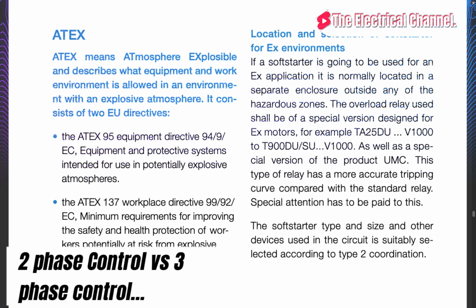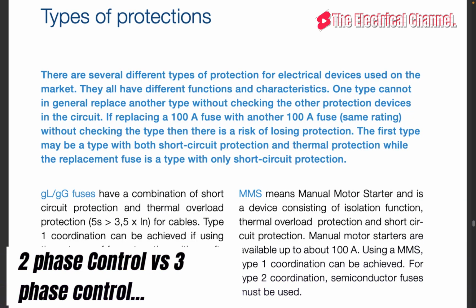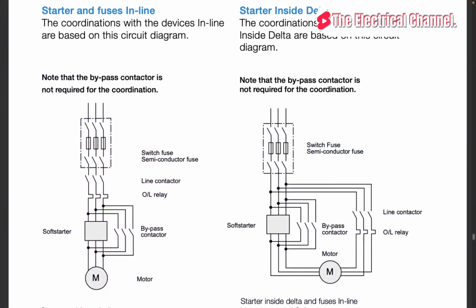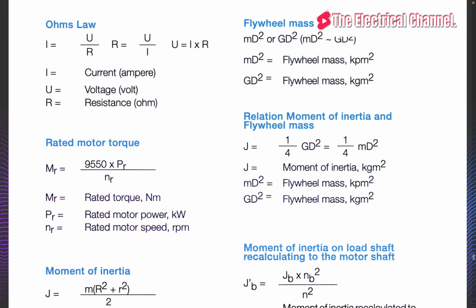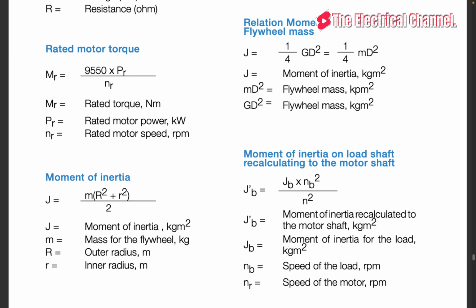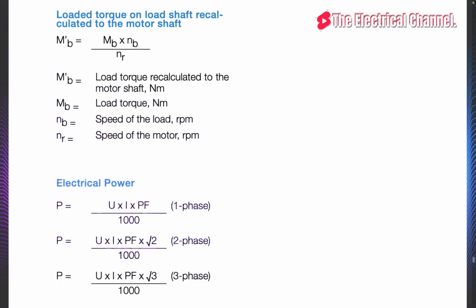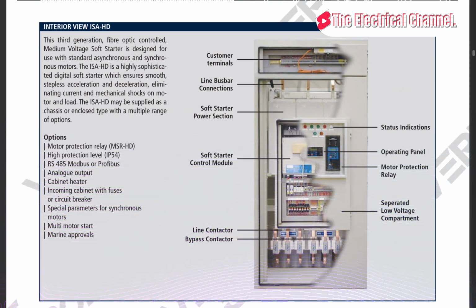Two-phase control versus three-phase control. Traditionally, a soft starter has used 6 thyristors, 2 anti-parallel connected in each of the 3 phases, to control the output voltage to the motor. However, in order to reduce the number of components used or to minimize the size of the soft starter, a solution where only 2 of the 3 phases are controlled is possible.